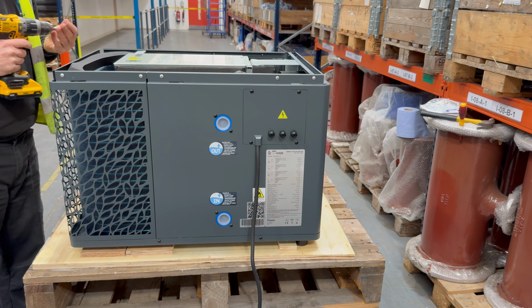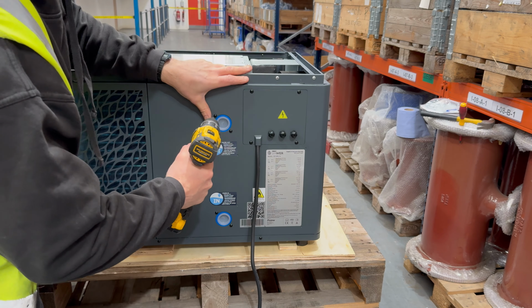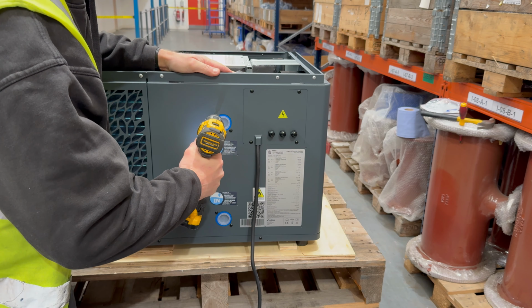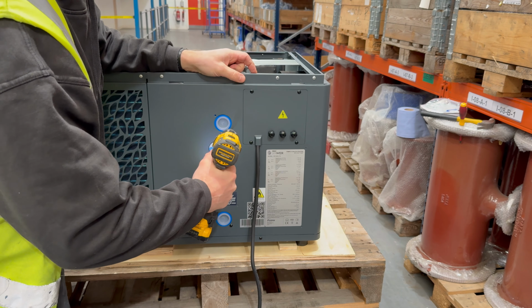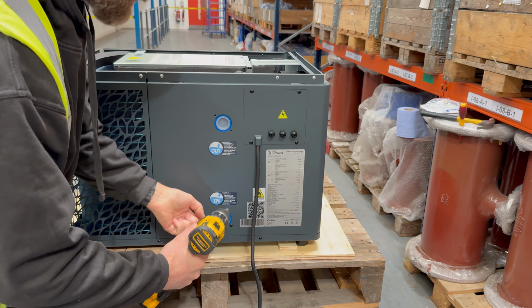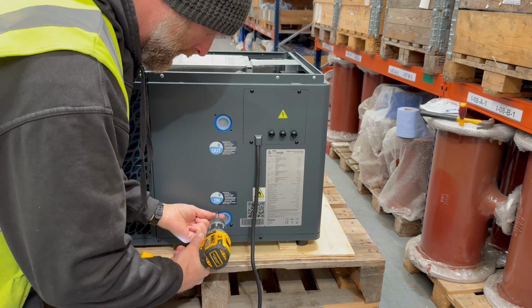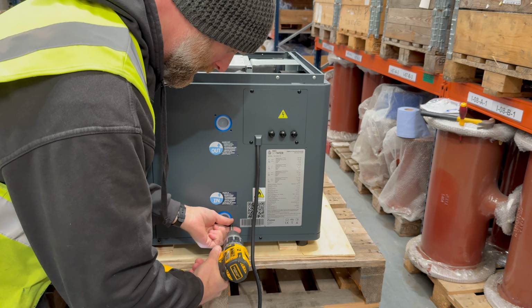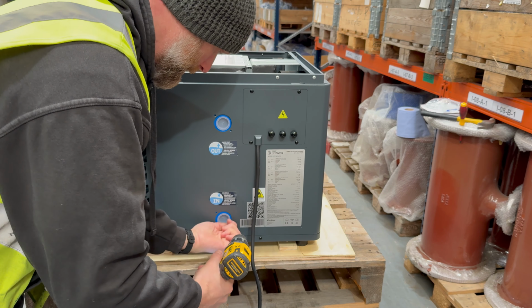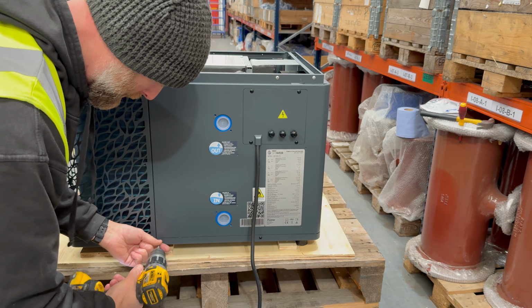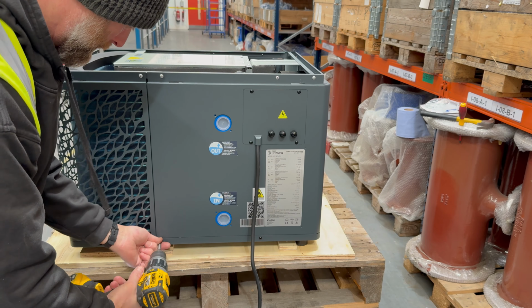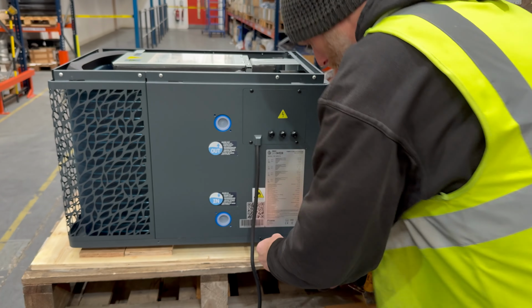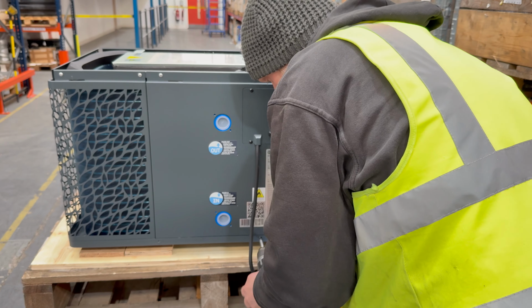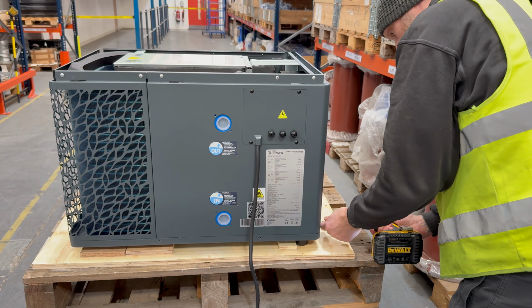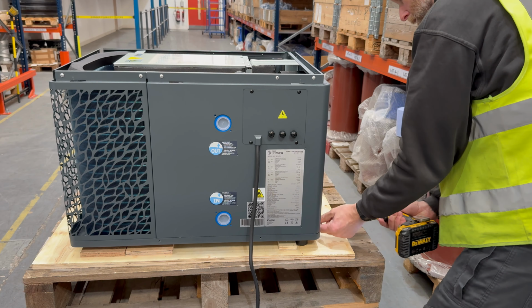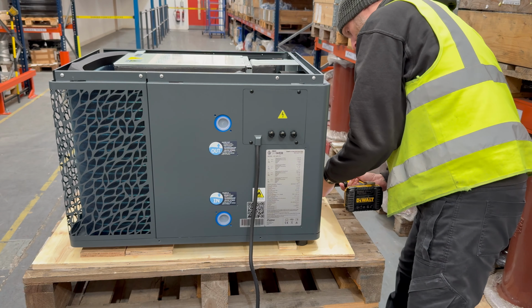Then we need to remove the panels on the side. First, undoing the port screws, the inlet and outlet screws that hold the heat exchanger to the side of the case. Then we undo the bottom screws, which you can see there, all the way around the side, which will allow us to take this whole right hand side panel off.